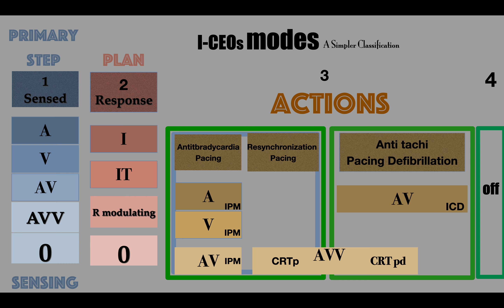Asynchronous IPM did not live long enough, as R-on-T was intimidating. Sensory function and inhibited triggered IPM response were added as a master program, while asynchronous pacing became a slave backup program. ICD, or implantable cardiac defibrillator, master program joined the pack, and ITIPM became its slave program. That would work in case of sudden bradycardia. So there is always a working master program, and in case it stopped or failed, the next in command slave program is activated.